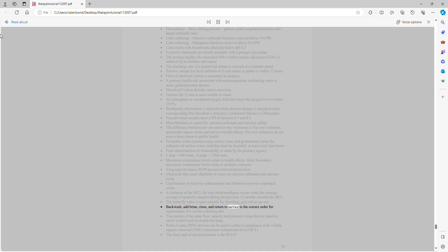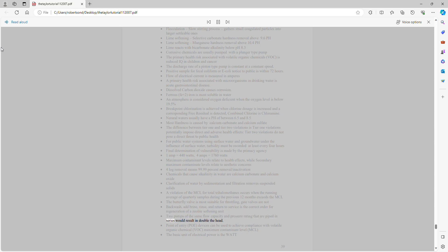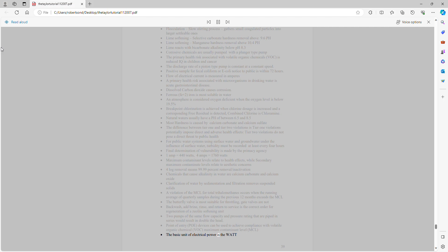Clarification of water by sedimentation and filtration removes suspended solids. A violation of the MCL for total trihalomethanes occurs when the running average of quarterly samples during the previous 12 months exceeds the MCL. The butterfly valve is most suitable for throttling; gate valves are not used for throttling. Brine, rinse, and return to service is the correct order for regeneration of a zeolite softening unit. Two pumps of the same flow capacity and pressure rating piped in series result in double the head. Point-of-entry (POE) devices can be used to achieve compliance with volatile organic chemical MCLs. The basic unit of electrical power is the watt.